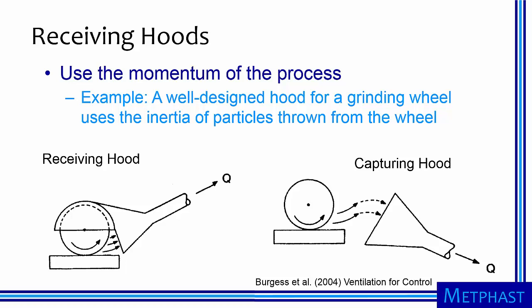The third type of hoods are receiving hoods. Receiving hoods use the momentum of the process to improve capture efficiency over other types of hoods. Here, we will consider a grinding wheel that throws particle contaminants with high inertia into the air. High efficiencies at low air flows can be achieved with a receiving hood aligned with the typical trajectory of particles thrown from the grinding wheel. In contrast, a capturing hood not aligned with the inertia of the particles is a poor choice because of the high velocities required to achieve high capture efficiency.